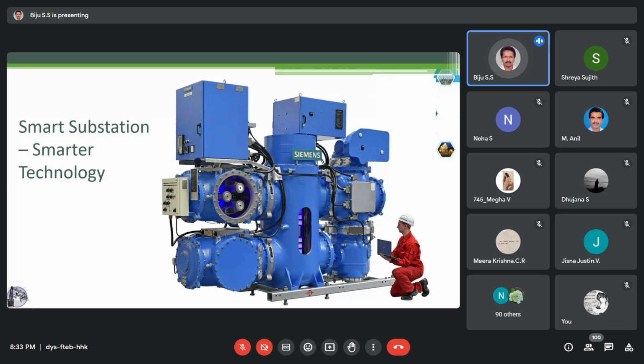So it uses clean air basically, instead of SF6. Clean air means 80% nitrogen and 20% oxygen. It's known as clean air. This is used for providing insulation. The interruption takes place in a vacuum chamber. The vacuum technology is used for interruption. Normally, in SF6 breakers, SF6 is used both as the interruption medium as well as for insulation. But here, insulation is through clean air and the interruption is through vacuum interrupter technology. So this is available now up to 145 kV, and it is already in service in Norway and Germany.